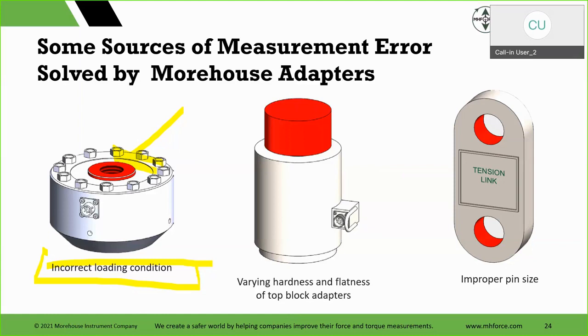If someone sends this type of load cell without the adapter, I don't want to send a cal out that's going to give them a 0.5% error. I want to know what they're doing so I can get that error down so they can replicate it within like a 0.01 or a 0.02. That's the goal. Now, if they lock an internal stud in there, they repeat within, you know, we could repeat all day long. That's a different story. That's the best solution to that equation: lock something in there, pull on it and push on it with it locked in.